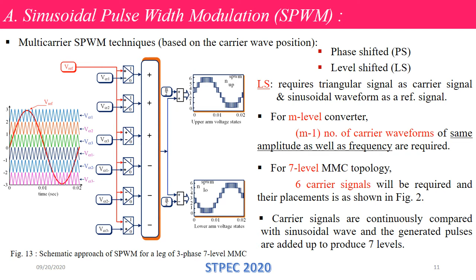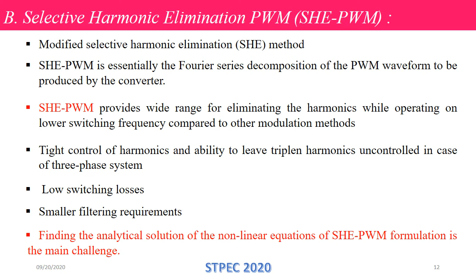Now the second one is selective harmonic elimination PWM. It is a modified SHE method and is essentially a Fourier series decomposition of the PWM waveform to be produced by the converter. It provides a wide range for eliminating harmonics while operating at low switching frequency, and it has tight control of harmonics. Also, it has the ability to leave triplen harmonics uncontrolled in three-phase systems. It has low switching losses, so smaller filter requirements. But the main challenge is that finding the analytical solution to the nonlinear transcendental equations for SHE-PWM formulation is quite challenging.